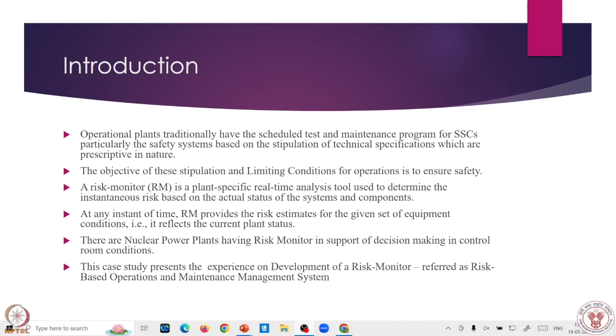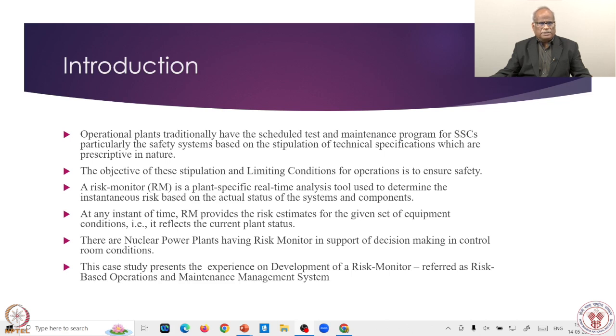This particular risk monitor module we are discussing only covers the R&D component of it — how the model was built. The traditional approach involves technical specification stipulations that operating staff must follow, stipulating limiting conditions for operation to ensure safety, maintenance intervals, and surveillance intervals for safety systems. The risk monitor itself is not entirely new; in many nuclear power plants it is already used in control rooms.